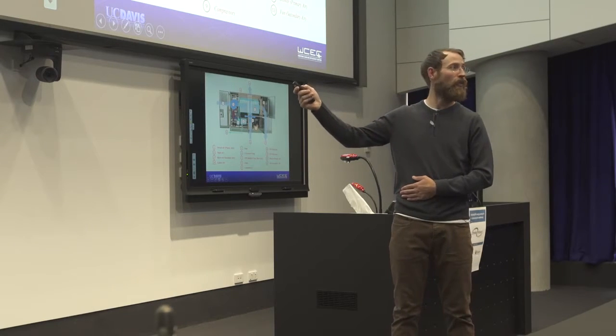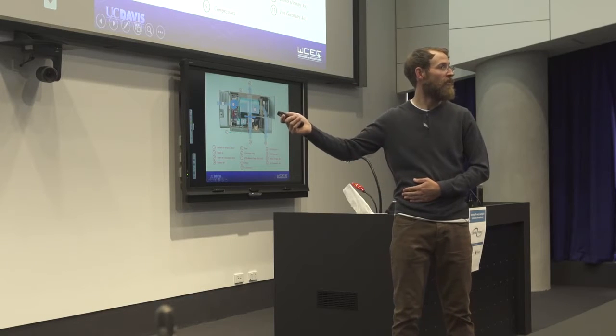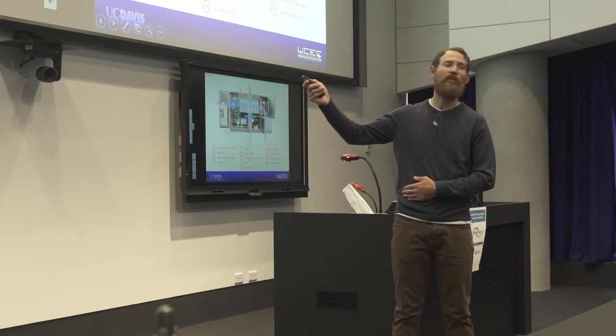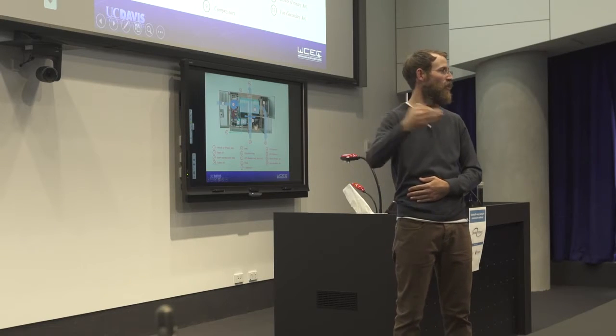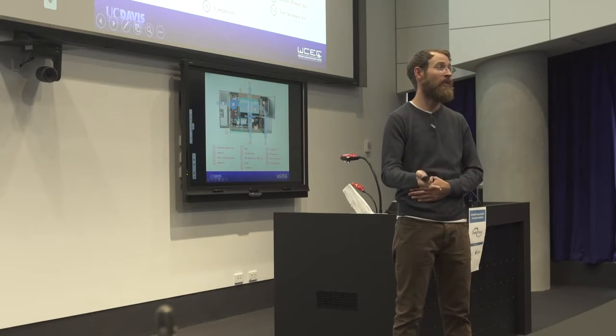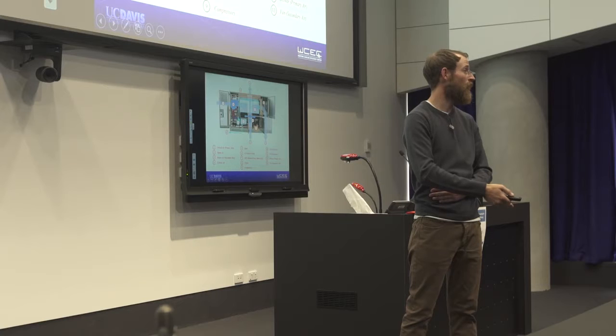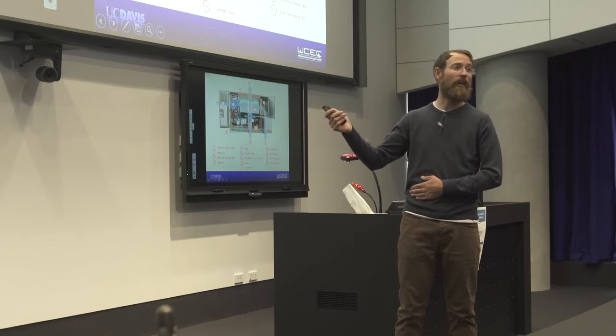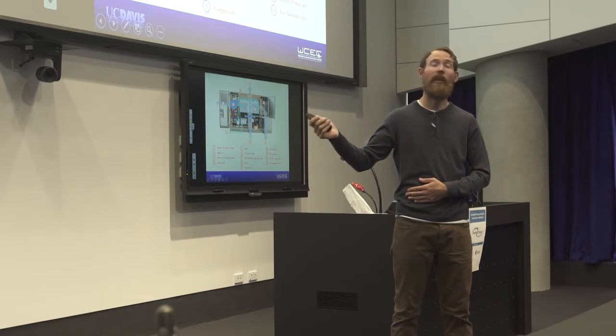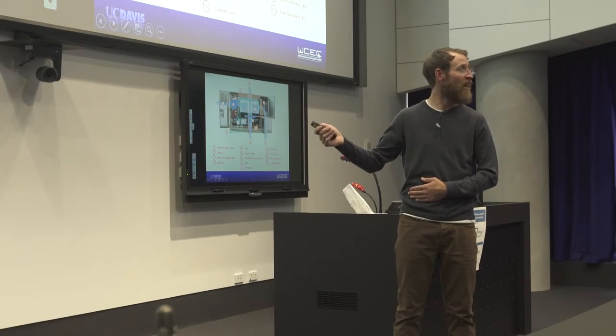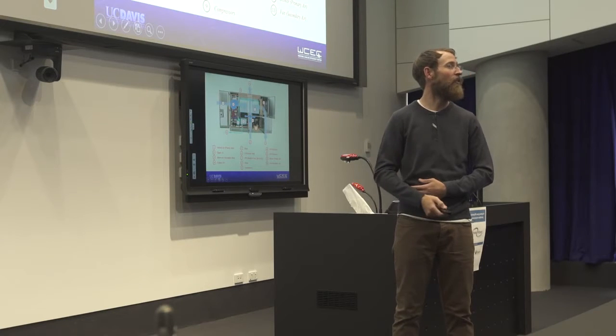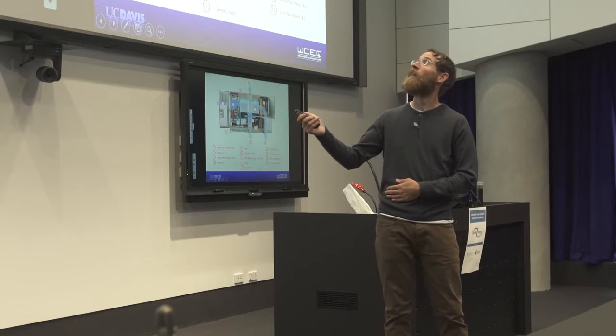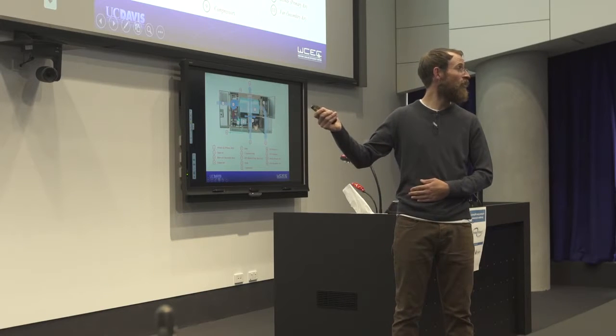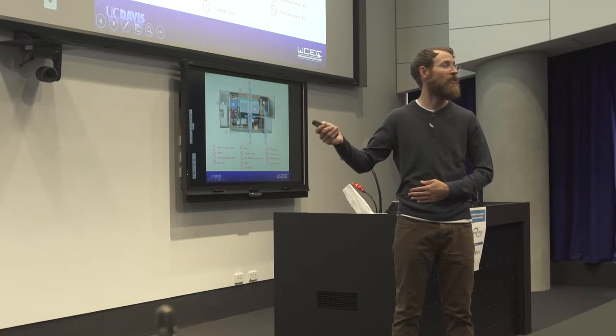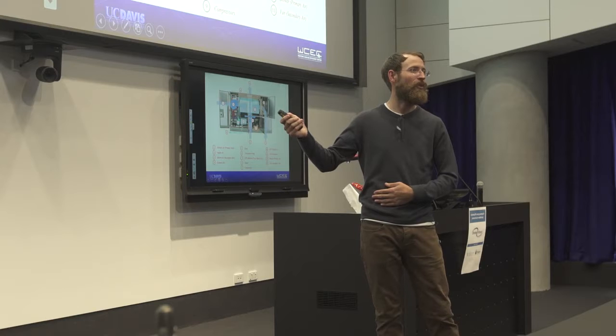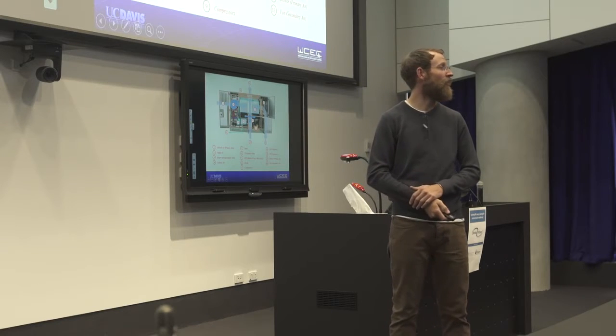This indirect evaporative core does not work in the same way as Seeley's system. It doesn't recirculate a portion of the cooled air back into the wetted channels, which is, by the way, what allows Seeley's system to drive the supply air temperature down below the wet bulb temperature. In this case, it's basically a tube and flow heat exchanger, and they utilize return air from the space as the source to drive the evaporative cooling process. So it can be configured to instead use outside air to drive that indirect evaporative cooling process, but they gain about 30% additional efficiency by instead using return air from the space.